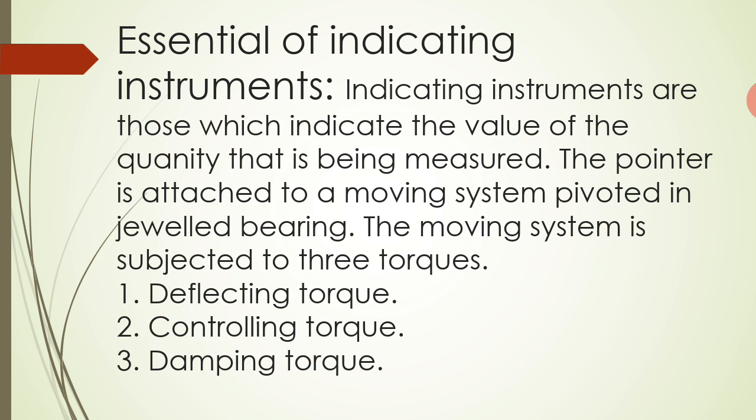Next is damping torque. Damping torque acts on the moving system of the instrument. During deflection, the controlling torque controls the deflection and tries to stop the pointer at its final position. But due to inertia, the pointer oscillates around its final position before coming to rest.